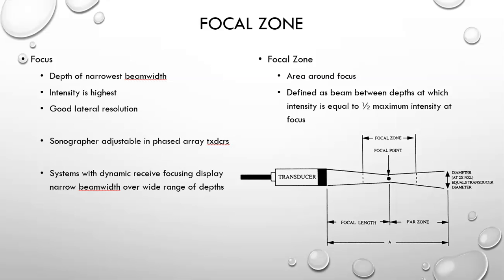You can evaluate the focal zone by looking at the depth of the narrowest beam width, and this is useful, but we did this in the lab when we were looking at lateral resolution, and we found that in many cases with our phantoms and our newer machines, it is very difficult to see any significant focal zone difference from the top to the bottom. However, it was much more dramatic on the older machines when we hooked those up and ran them.